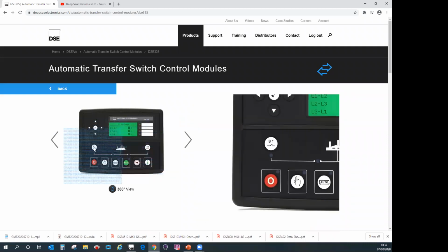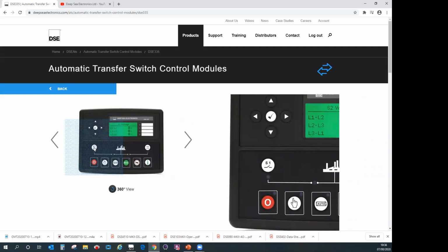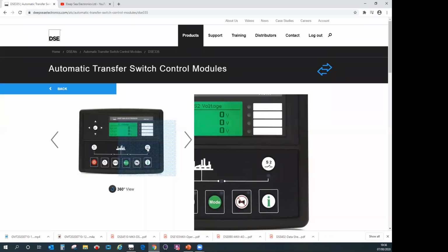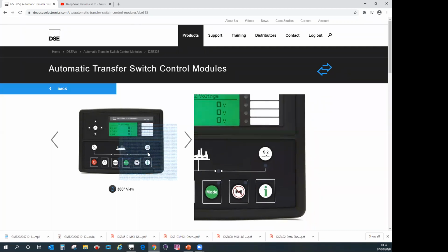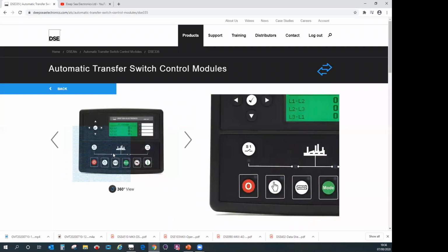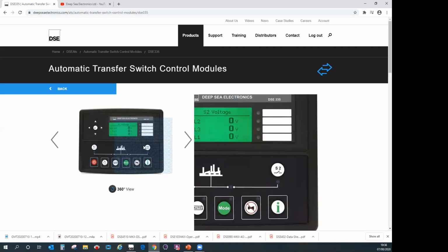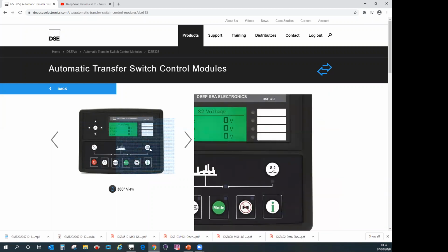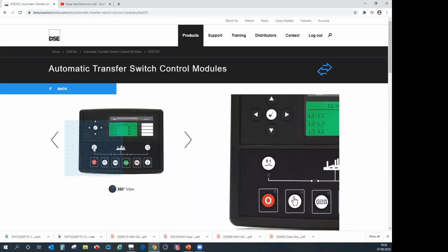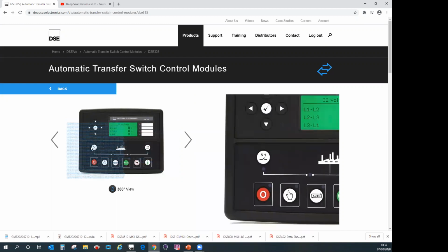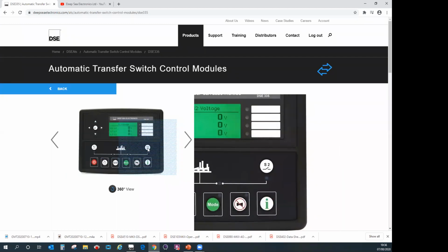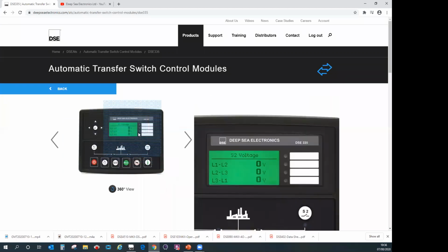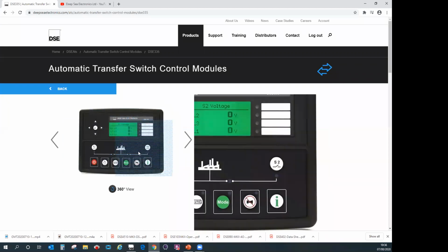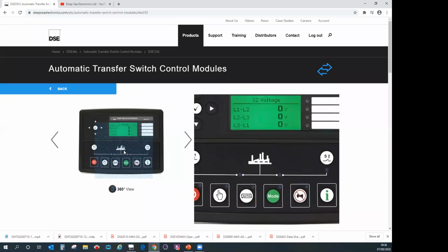So what you might see is supply 1 is maybe the main supply, and supply 2 would be a generator, okay? Or it might be two generators or three generators, but all supplying that one supply. When that supply becomes available, it closes its breaker and transfers the load from S1 to S2. It could also be the other way around: S2 could be the mains, S1 could be the genset. Or it could even be S1 is one main supply and S2 is another main supply. The thing with the 335, it's not a genset controller, it's an ATS controller, so it's controlling a transfer switch.